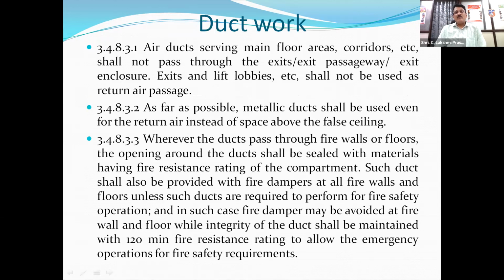Then air ducts serving main floors and corridors shall not pass through exits. This is a very, very important provision, where these air ducts should not pass through the escape route, that is corridors or exits, passageways, exit enclosures, exits and lift lobbies, etc. They shall not be used for return air passage, because return air will be hot in temperature. So it is not allowed to pass through these escape routes. As far as possible, metallic ducts shall be used even for the return air instead of the space above the false ceiling.